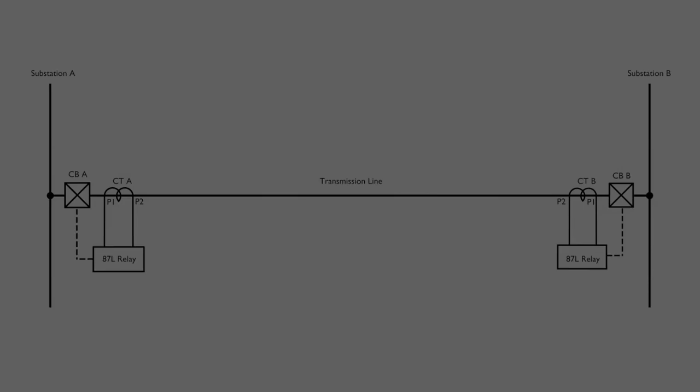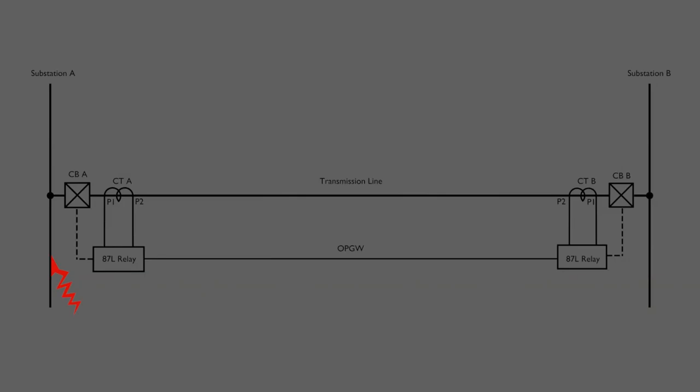Now we shall draw line differential relays with the current transformers. The relay activates the tripping of associated circuit breakers. Line differential relays are generally numbered as 87L. The differential relay at both ends of the transmission line is connected to an optical fiber. OPGW is used for this purpose.